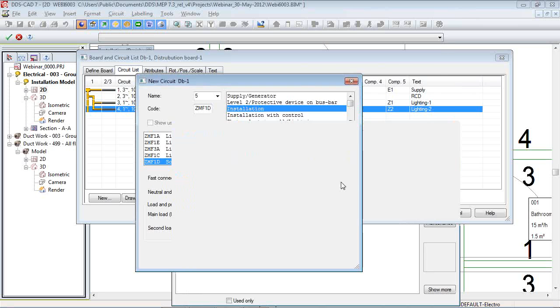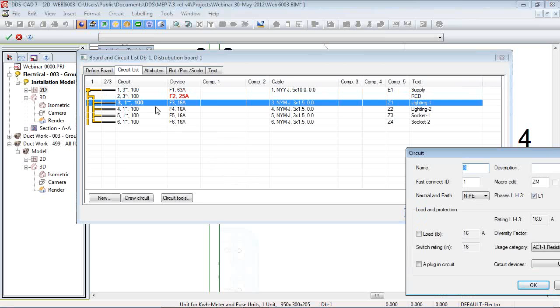On our main distribution board, we want a supply of 63 amp protective device with a B-type circuit breaker. We have to choose what kind of net we're using, and from the net we can say we'd like RCD protection - an RCD protection of 25, with 30 milliamps protection.